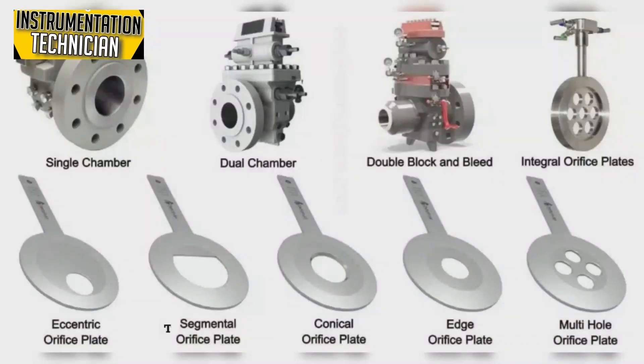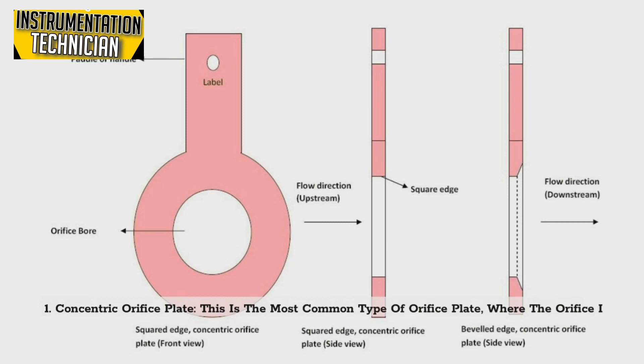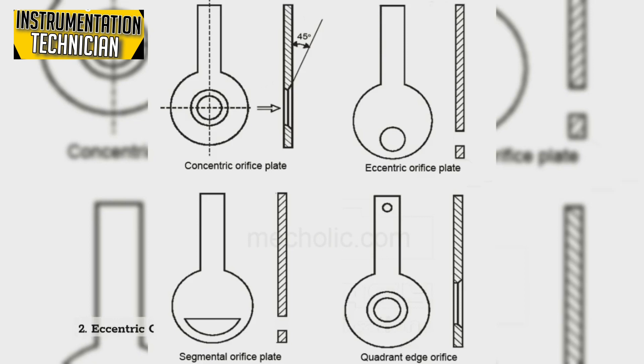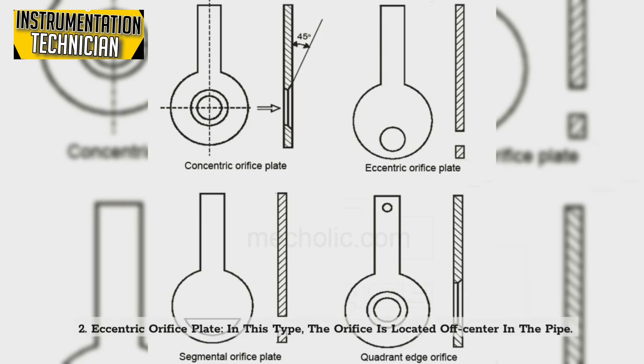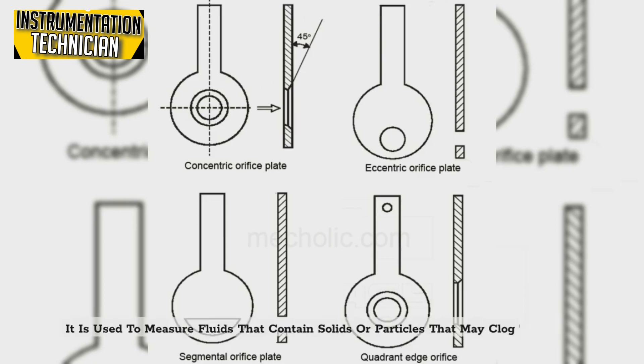There are different types of orifice plates, including: 1. Concentric orifice plate — this is the most common type, where the orifice is placed concentrically in the pipe. 2. Eccentric orifice plate — in this type, the orifice is located off-center in the pipe. It is used to measure fluids that contain solids or particles that may clog the orifice.